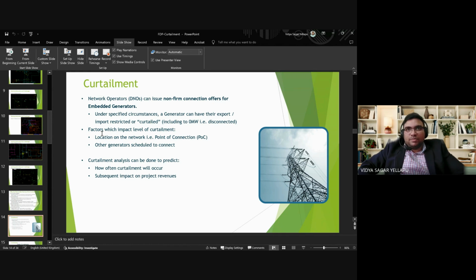Factors that impact the level of curtailment are the location of the network, the location of this particular generator on the network, and other generators scheduled to connect. If there are many other generators in the surrounding region sharing the same existing network, those will compete for the capacity of those constrained assets. That will be a challenging situation for the generators that are behind in the queue. Curtailment analysis is to be done to predict how often curtailment will occur for a particular generator, and what the subsequent impact on that project's revenues will be.